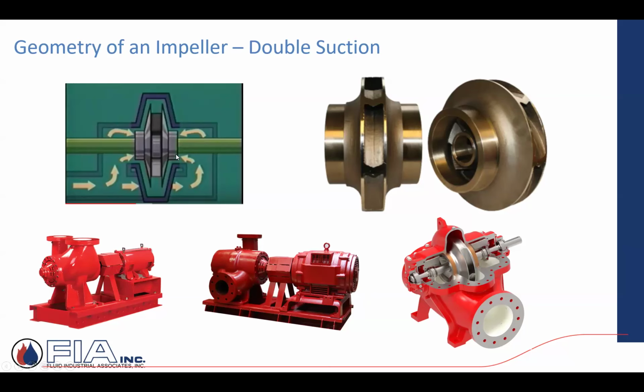The reason for that is you're getting into really higher flow rates, higher capacity pumps. If you were just taking that traditional end suction pump and putting all of that flow, all of that force on the bearings, shaft, and seals, it can get pretty excessive. With this double suction, they almost cancel each other out. Instead of hitting it with one, you're evening it out. The flow comes in equally, and that's what they'll do, take whatever that flow rate is and equally split it so that it enters equally into each side of that eye, to evenly load and take away that thrust that's taking place on the bearings. Single suction is less expensive and more appropriate when the loads are low, but when the flow rates get higher, it makes more sense to move into this double suction arena.